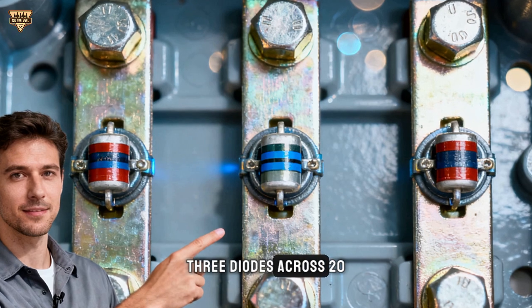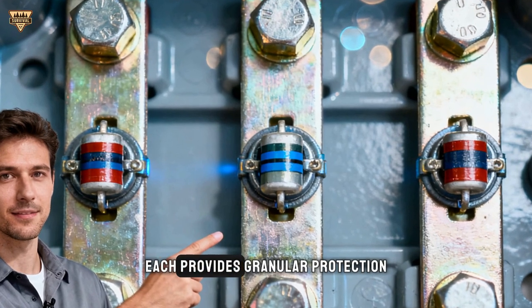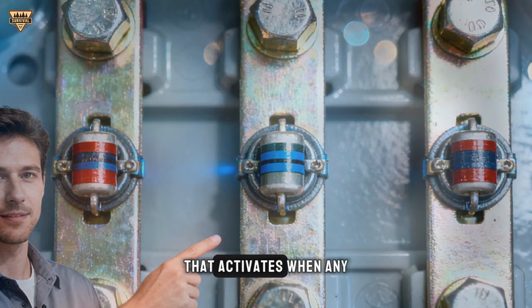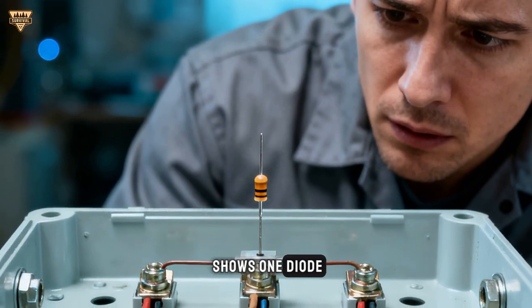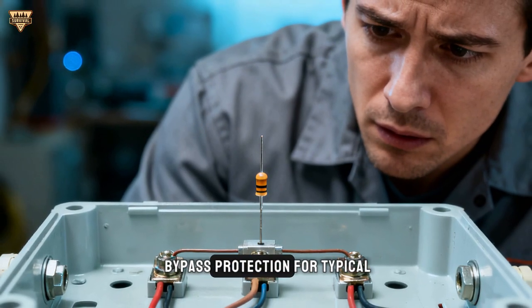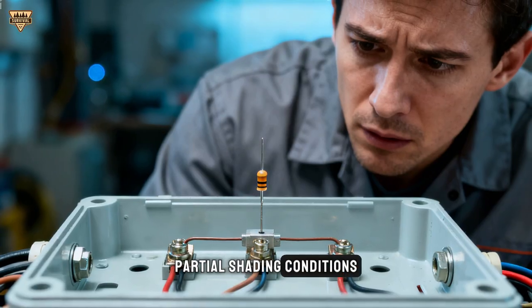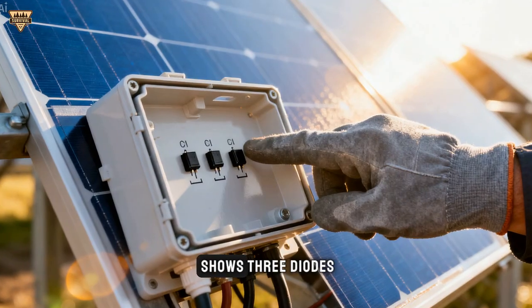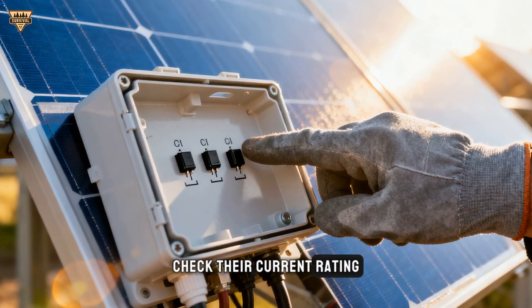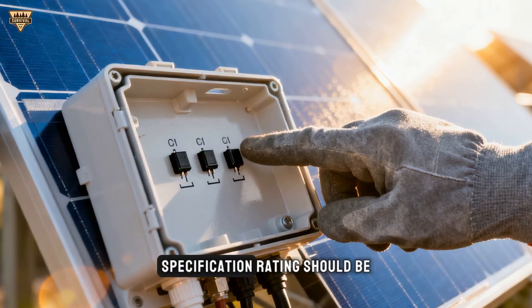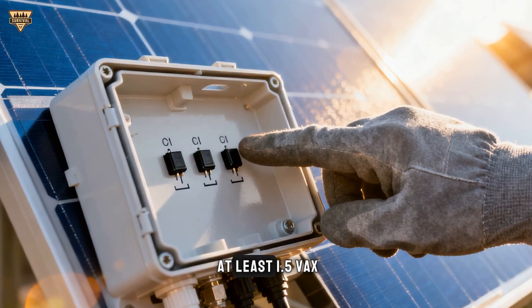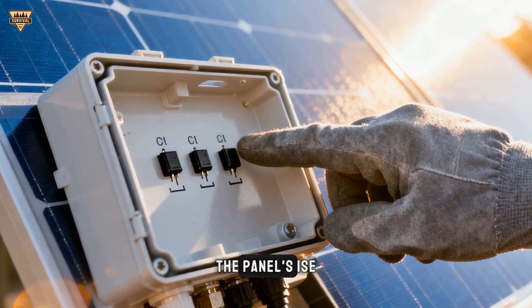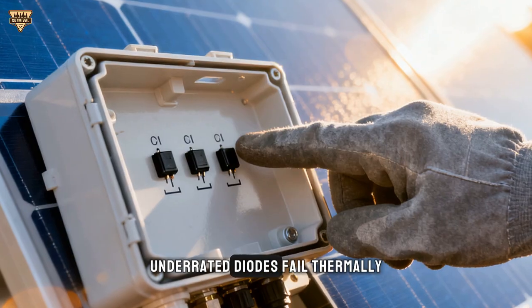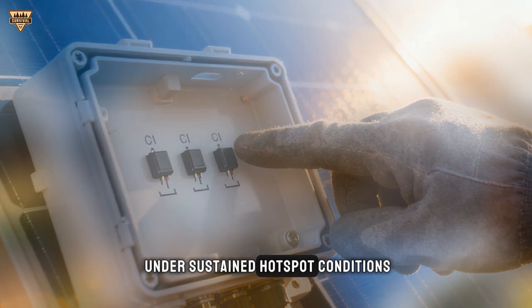3 diodes across 20 to 24 cell groups each provides granular protection that activates when any cell group experiences shading. If your junction box shows 1 diode, your panel has inadequate bypass protection for typical partial shading conditions. If your junction box shows 3 diodes, check their current rating against your panel's short circuit current specification. Rating should be at least 1.5x the panel's ISC. Underrated diodes fail thermally under sustained hotspot conditions.